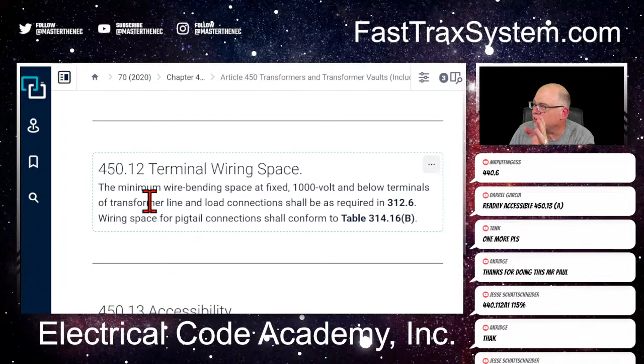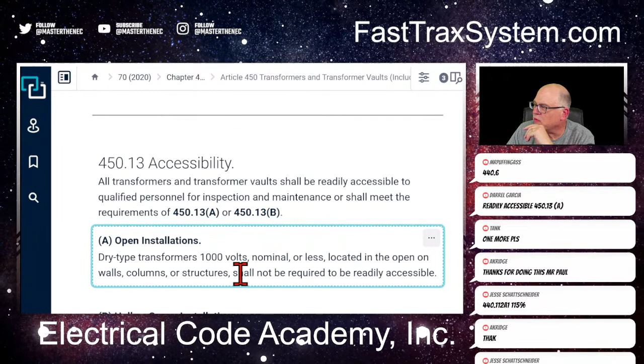Open installations, dry transformers, 1,000 volts—ding, ding, ding, ding, ding, all these things are in the question, okay? Dry type transformers, 1,000 volts nominal or less, located in an open area on walls, columns, or structures, shall not be required to be readily accessible.